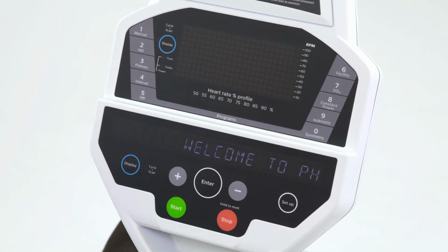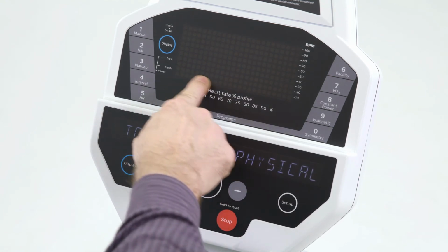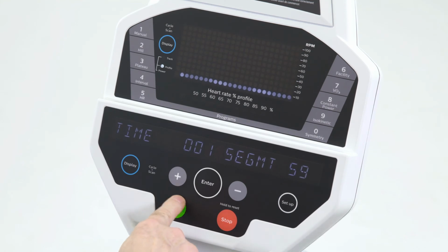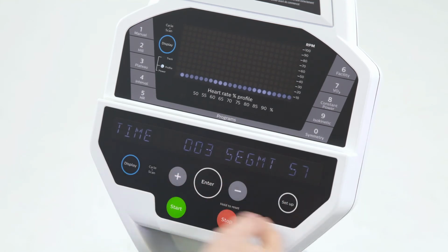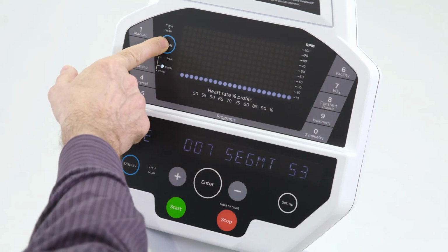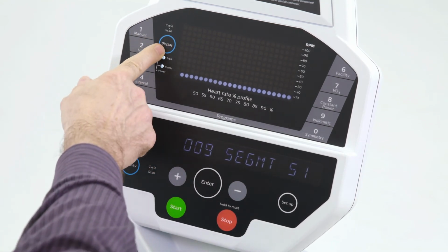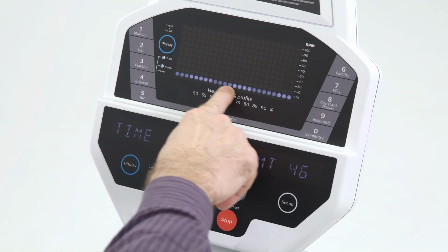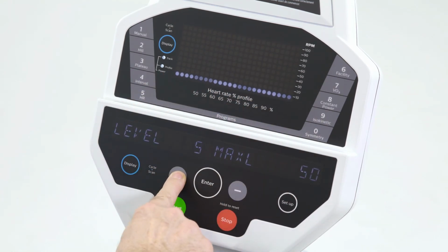In the setup, we are able to set how many watts per row on our display, so I'm going to show how that works. Right now, the default is 10 watts per row, and I have 1 row of lights. If I press the display button, both of these light up, which indicates I am now on the power display. So this now indicates power.